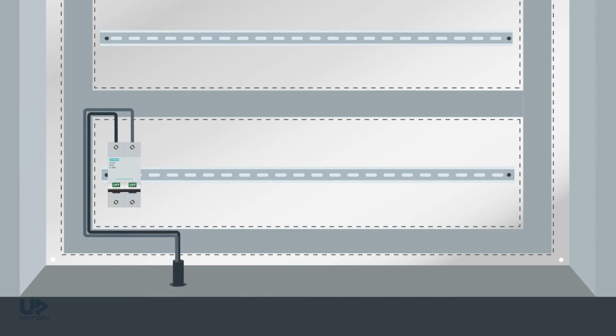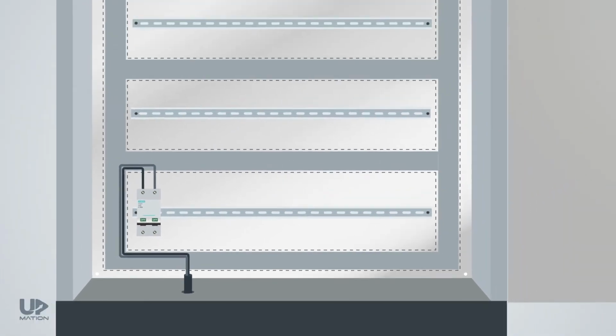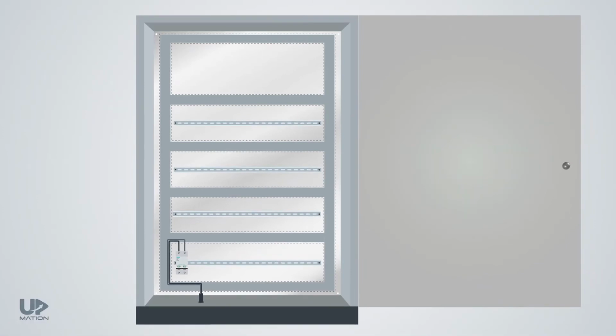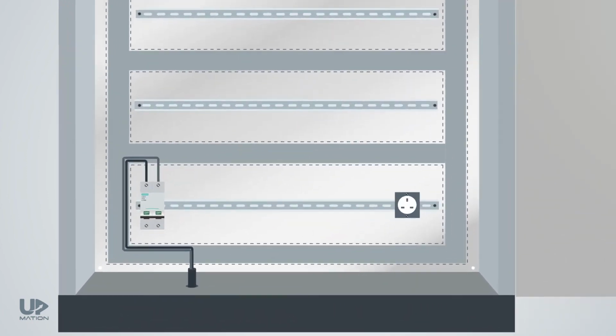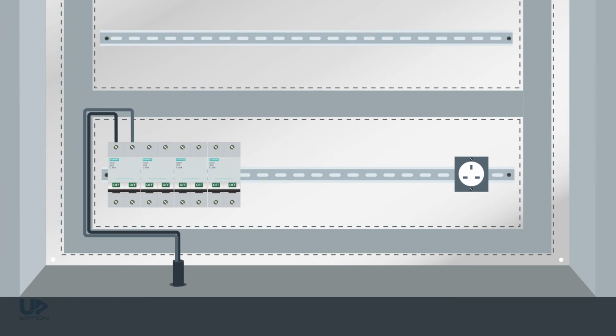Now that we have electric power inside, we should distribute it between different devices. First, we need to supply the utilities of the control panel, like the lamp, fan or heater, and socket. Let's consider a separate MCB for each of these devices. The standard way to connect the wires to an MCB is to connect the input wires to the top side and the output wires to the downside connectors.